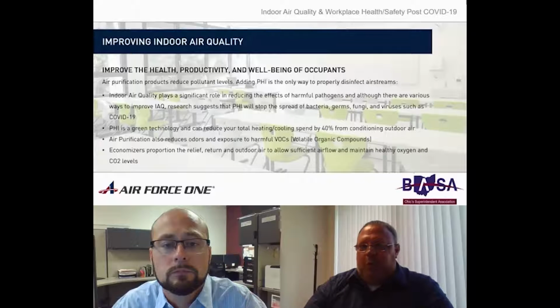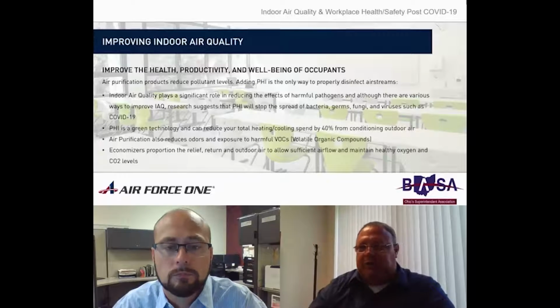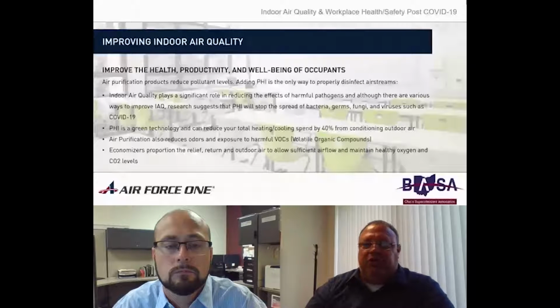What I want to add is we just talked about cooling towers and the fact that they can actually pollute the air pushed back into the space. Before that, we talked about filters, which can be affected by that. We also talked about ventilation, and the last part of our slide is your economizers, which allow outside air to come in and allow air inside the space to be exhausted. That's more of a traditional system. Some newer schools and buildings have outdoor air systems doing heat recovery. Those units still act the same way, you're just getting some recovery on it. So even if it's 100% outside air going through an energy recovery wheel, it still has an impact on indoor air quality.